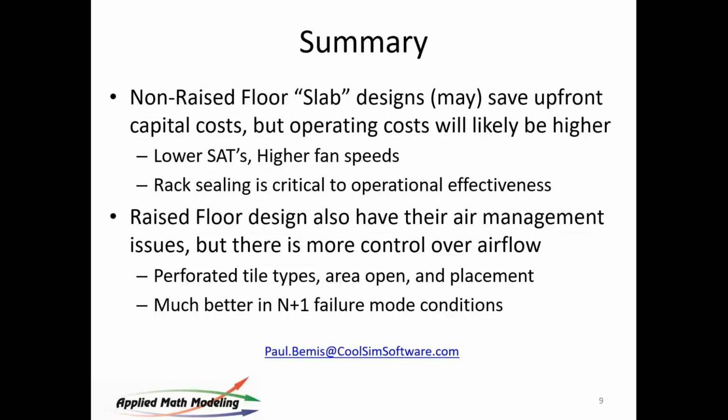On the opposite side of the CRACs, if I install perforated doors on the racks and try to reduce the pressure, do you think you can improve the temperature of the racks? Yes, Diego, there's many things you can do to modulate this from the operational point of view, but it's an operational issue. You have to be there. In other words, someone has to do that, and the people who are operating the data center need to be taught important issues like management of that air.